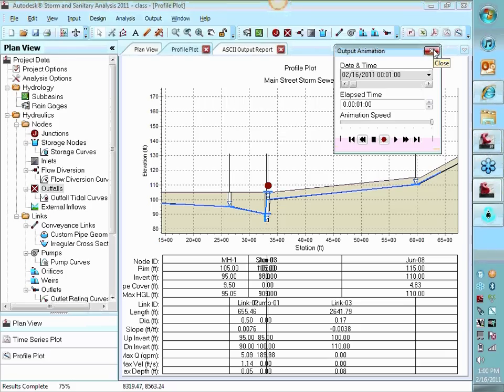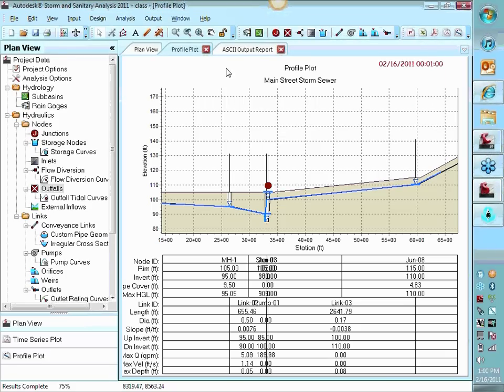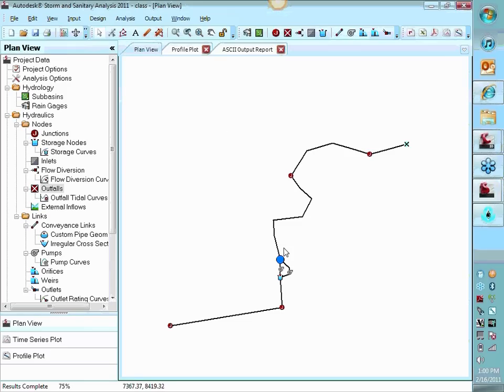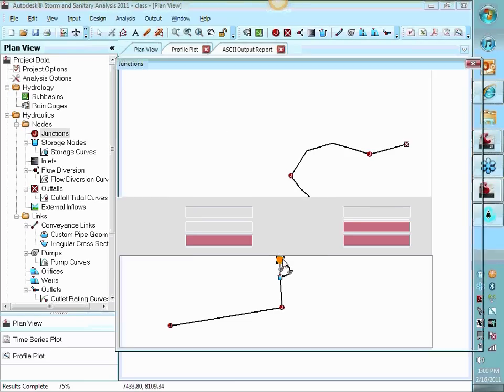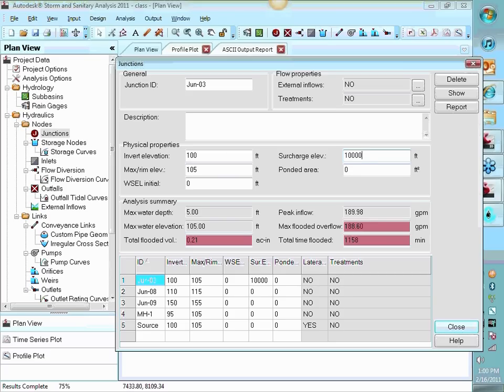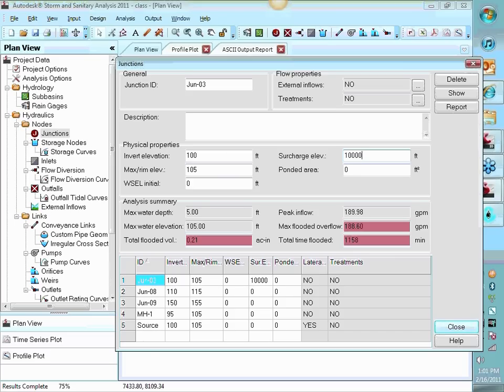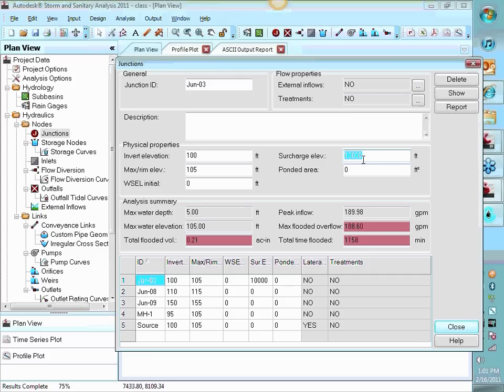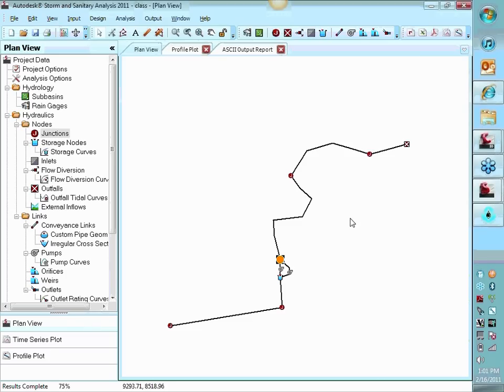What is going on there is that we're restricting the model. This took me a while to figure this out. When you're doing a pressure system model, you have to not restrict that hydraulic grade line. So by restricting that, leaving that at zero means essentially the hydraulic grade line is set at the invert of the pipe. So when the pumps turn on, there's an immediate loss of water. So the rest of the system never sees any water. So if the pumps turn on, it goes into that first pipe and it disappears because my surcharge elevation was zero, which by default it will bring it up to 100. So I need to make that some ridiculously high number. 10,000 seems pretty high and ridiculous to me.